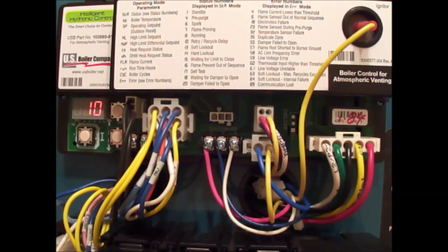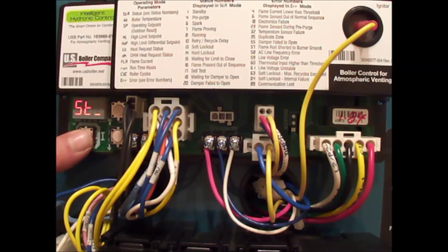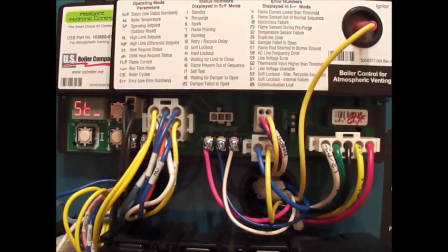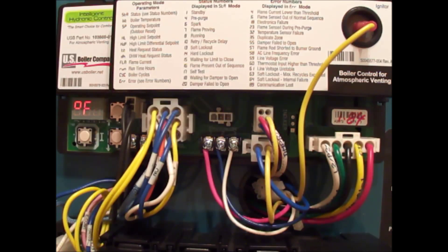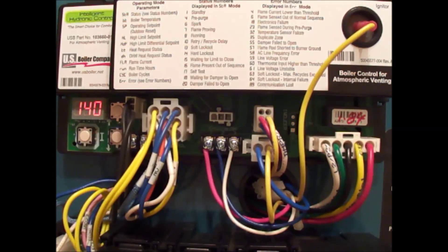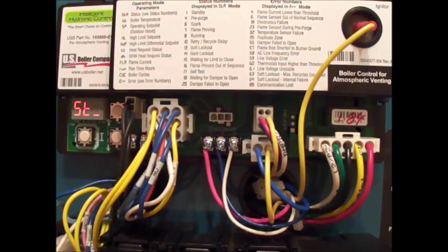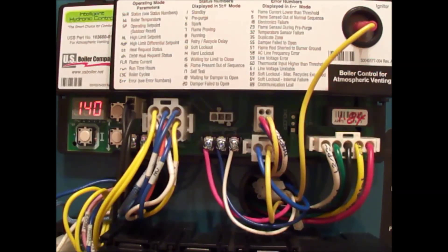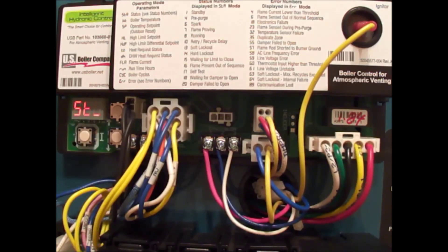The next one is start temperature. We can change the start temperature—I said it has to get below 140. We can raise that depending on your application. If you have kick space heaters or duct coils in your heating system, you may want to change that. But bear in mind there's not much water volume in these boilers, so it normally wouldn't take very long to drop the temperature, and the higher you make that, the more fuel you're going to use.